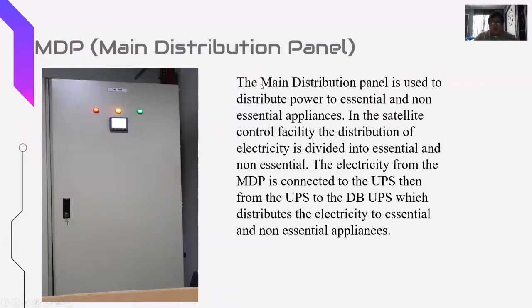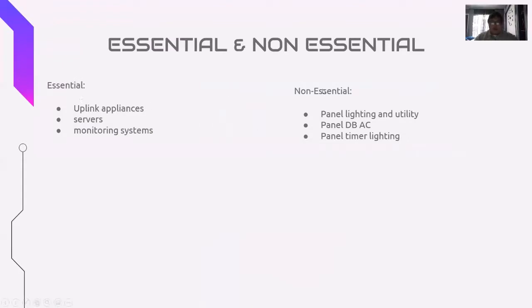And the MDP, the main distribution panel, is used to distribute the power to essential and non-essential appliances. In this satellite control facility, the distribution of electricity is divided into essential and non-essential. The electricity from the MDP is connected to the UPS, and from the UPS to the DB UPS, which distributes the electricity to essential and non-essential appliances. Essentials are basically uplink appliances like antennas, KPAs, which we'll get to later, servers, and monitoring systems. The non-essentials are panel lighting and utility, which controls all the lighting in the facility, and the DBAC, which controls the AC in the rooms. And then timer lighting, which is a timer that turns on the lights in the antenna area when it reaches 5 p.m.